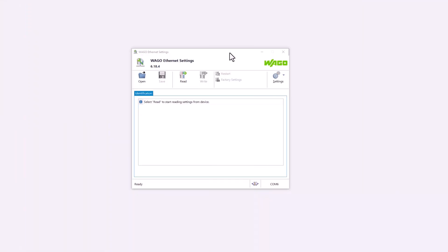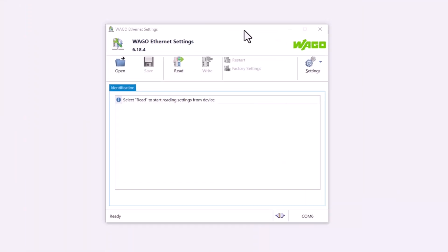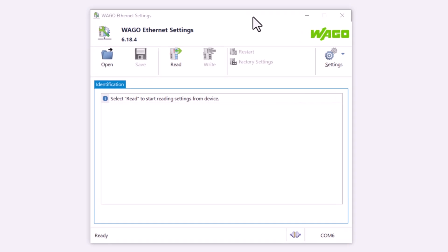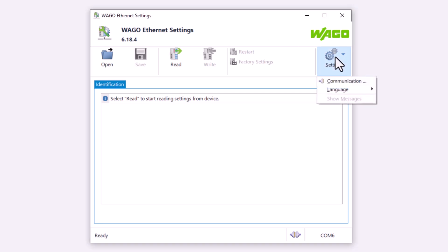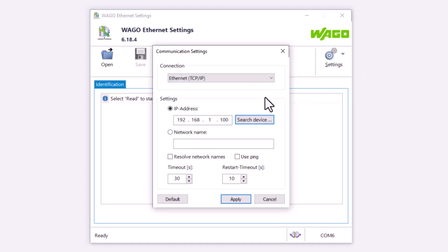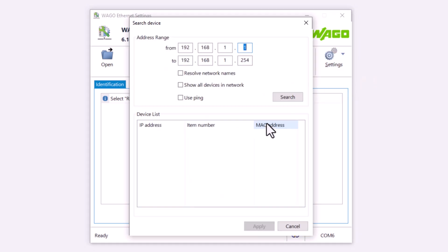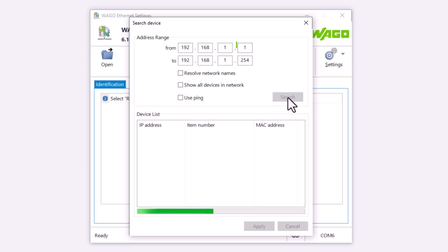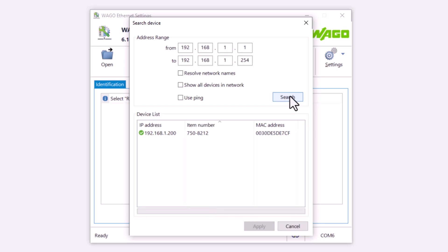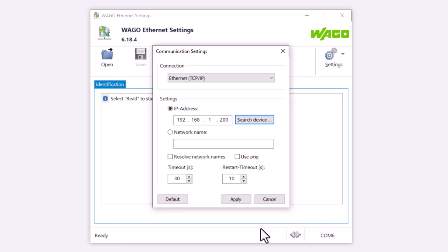Another way to find a controller is to scan the network. This is also possible with WAGO Ethernet settings. If the controller is running on a particular network and has received any IP address in the subnet, either via DHCP or statically, we can scan an address range in the communication settings in Ethernet settings using the Search button. In this case, we are on the 192.168.1 network and are scanning all possible network addresses from 1 to 254. This will take some time, but our controller will be found and its IP address will be displayed.